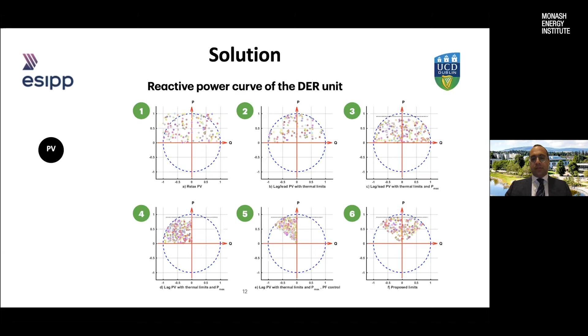So the question you might ask here is, how can we understand how much Q we should inject into the grid? This is the technical constraint that we have at the moment, but we need to find an intelligent way to understand how much Q is required for that specific snapshot of the operation. So here we developed a 3-phase optimal power flow tool, and we fed it the data of the network and the technology connected to the grid: the network topology, impedances, and the connection points of DERs and loads. The technology and the limitations of the inverters are also fed to the model. Then we ran offline simulations of different scenarios that we might face in reality. When I say we, I mean the distribution network operator. So this data is injected into the model.